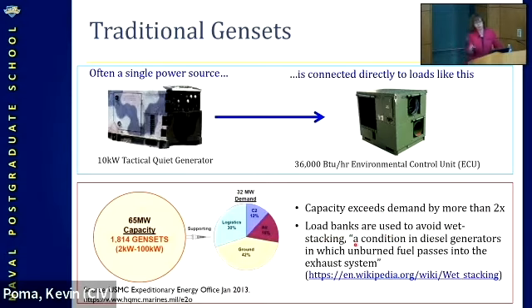Wet stacking is a term that is not easily known, so I copied it from Wikipedia - it's mostly for mechanical engineers to know. It's basically when the generator is so lightly loaded that there is unburned fuel in the exhaust system, and this reduces the lifetime of the generator. So the generator will last less if you operate it at light load all the time.